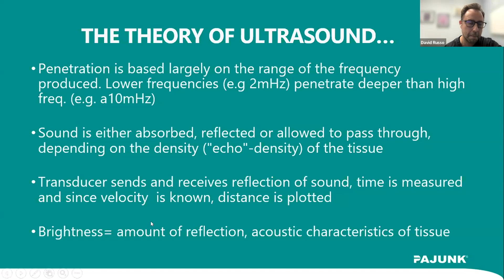Most of the manufacturers have really gotten the electronics of the image processing piece of the equipment down to a very fine science, but you really want to ask about the frequency of the probes, their durability, the kind of arrays, the piezoelectrodes, because that's really going to be the piece of the equipment that's responsible for generating the best image quality. So things that appear bright on the ultrasound image are things that are reflecting sound waves back to the probe. Things that appear darker on the ultrasound image have more water content, and that represents sound waves being transmitted through the tissues. So next slide.